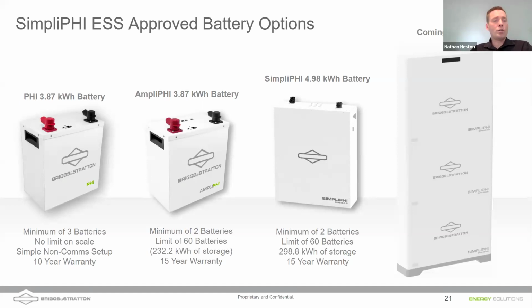With the Phi battery, you can do almost no limit on the scale. I'll show you a few pictures later of very large systems using the Phi battery. You do have a limit of about 60 batteries on the AmpliPhi battery, and that has to do with the communications equipment on those batteries. The same BMS in the AmpliPhi battery also appears in the 4.98 kilowatt hour battery. The difference between these batteries is, one, the 4.9 battery is a wall-hung battery. You still have a limit of 60 batteries there. You can do up to 300 kilowatt hours of storage with these batteries.